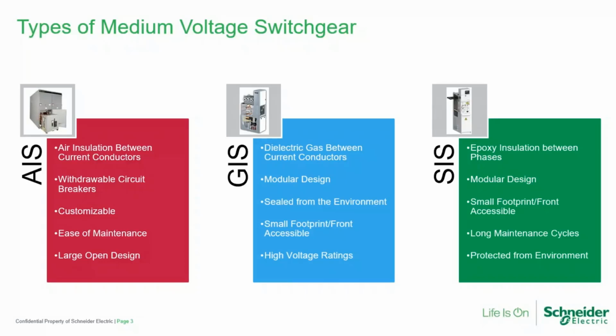If you look at the history of medium voltage switchgear, the current designs of metal enclosed switchgear, fused switch style metal enclosed switchgear, had their origins in about the 1950s and 60s. More modern metal-clad withdrawable vacuum circuit breaker medium voltage switchgear designs had their origins in the late 70s, and for a lot of companies currently selling them today, in the early to mid 80s. And to tell you the truth, designs haven't changed a lot on those two broad categories until maybe the past 10 years, when switchgear manufacturers have started to develop newer types of medium voltage switchgear and newer applications of the existing styles.